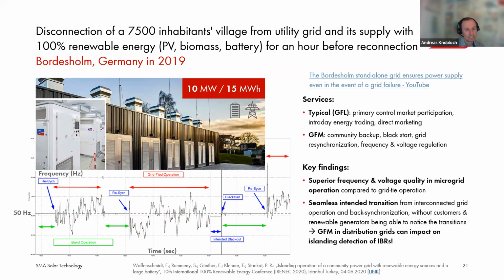Another key finding was the seamless, intended transition from interconnected grid operation to island operation, and also the back synchronization. And the important part here was that the consumers within the grid, but also the renewable generators, haven't noticed the transition. That also means we had some grid-following systems like PV systems within this grid, and their islanding detection mechanisms have not detected an island situation.